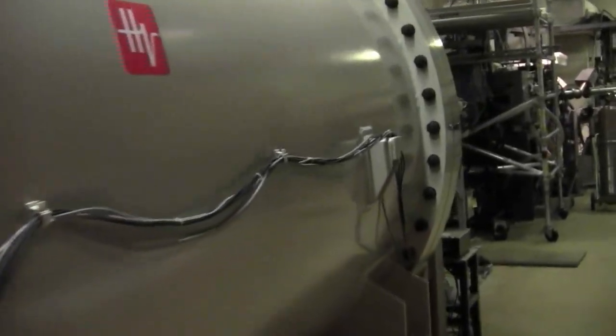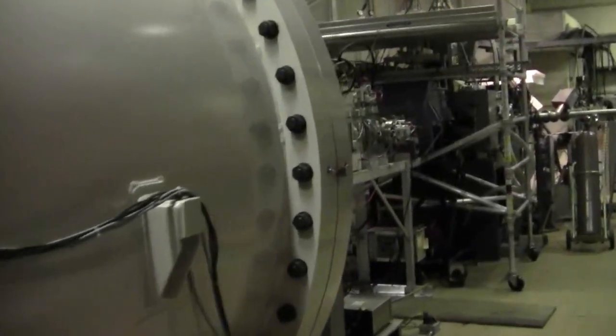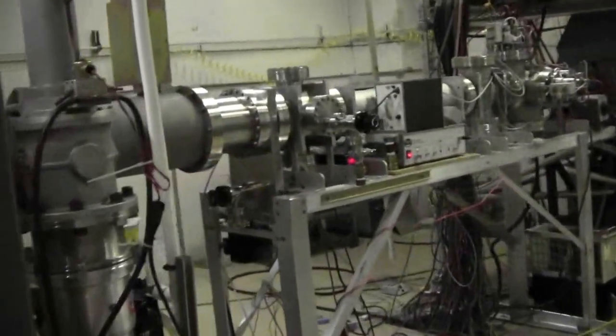We are passing alongside the acceleration column that separates the high voltage terminal from the front end of the accelerator which is at ground potential. The ions gain energy as they move through this tube.